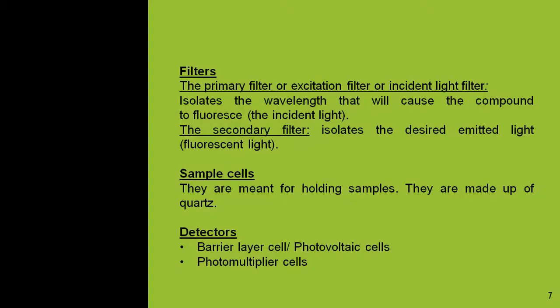As we have discussed, two filters are used: one is known as the primary filter and another is the secondary filter. The primary filter is also known as the excitation filter or incident light filter. This filter isolates the wavelength that will cause the compound to fluoresce, allowing the light of interest to be incident on the sample. The secondary filter isolates the desired emitted light, that is the fluorescent light.